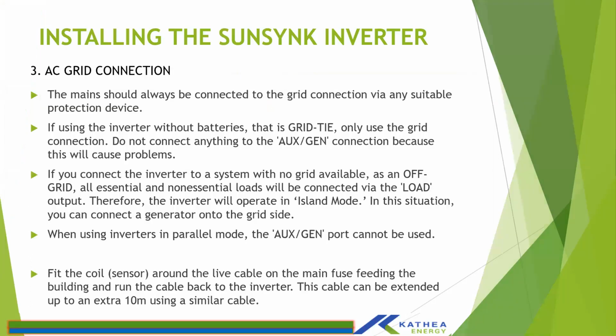And then installing the AC grid. AC mains should always be connected on the grid point. So when you're installing your grid input, it should always be installed on the grid point. If however you install it on the Aux port or load port, and it damages your inverter, it will not be covered under warranty. So you should always make sure that your grid incomer is installed on the grid point on the inverter.